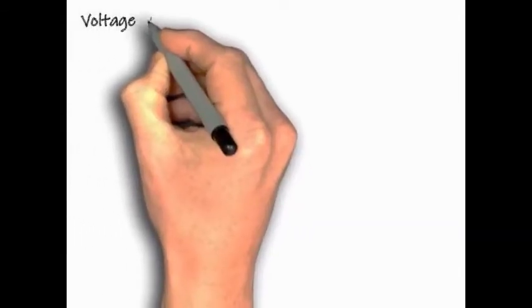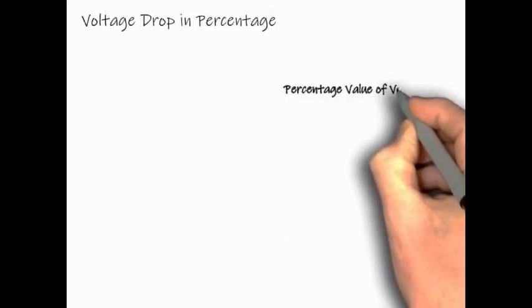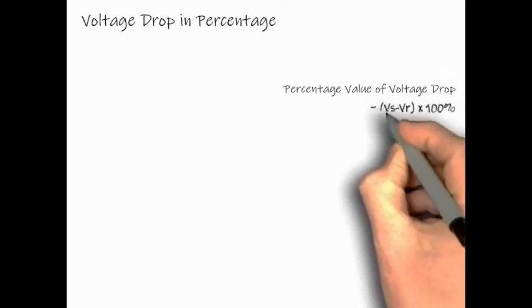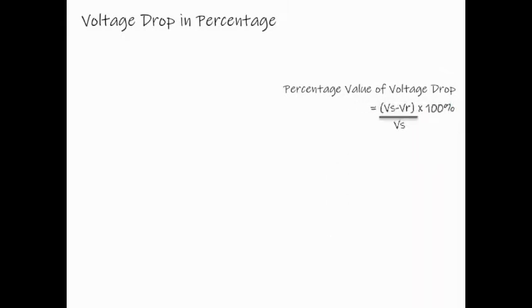Voltage drop can be expressed in percentage. Percentage value of the voltage drop equals to Vs minus Vr divided by Vs multiplied by 100%. The advantage of expressing voltage drop in percentage is that they can be added together directly. Vs is the sending end voltage which can be a nominal value of the supply voltage. Vr equals the voltage receiving end.